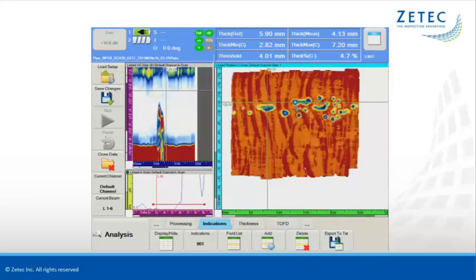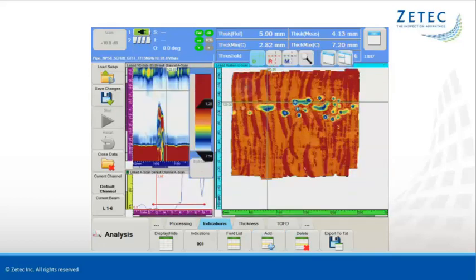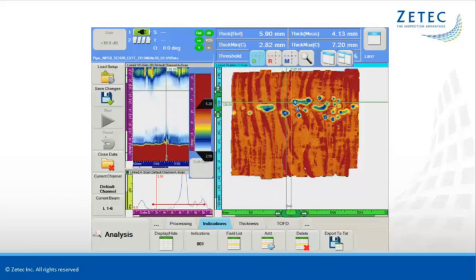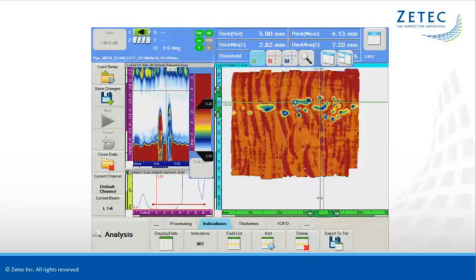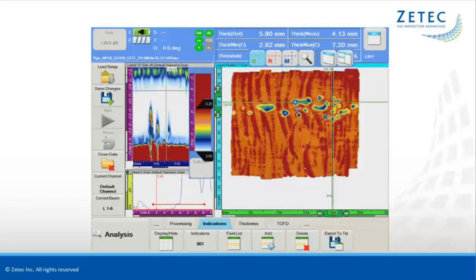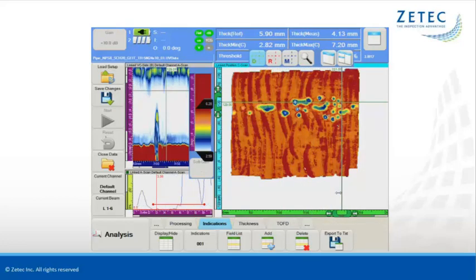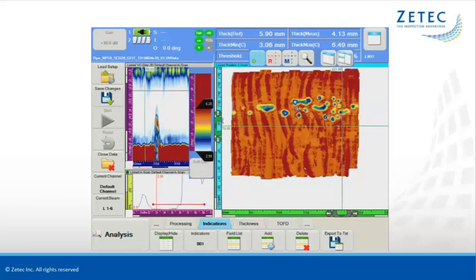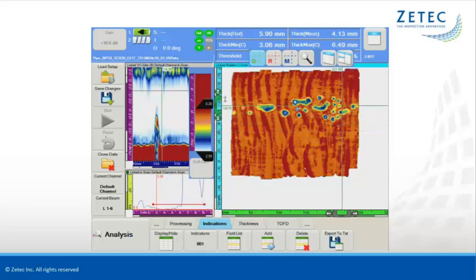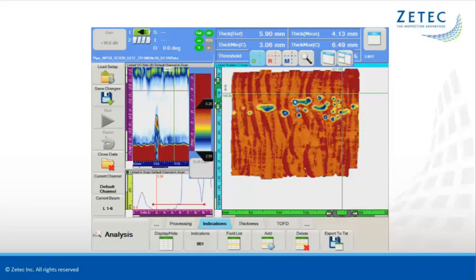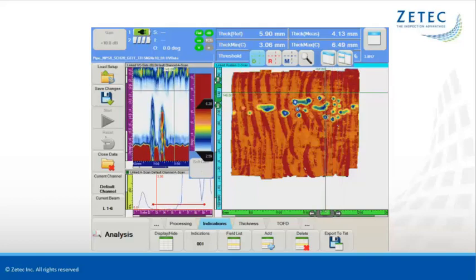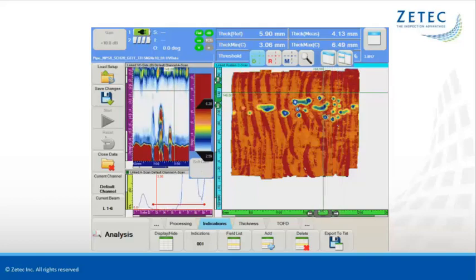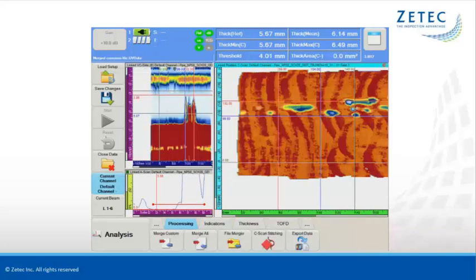Dedicated info fields for corrosion damage assessment display key information about the surface area shown on the screen. Minimum and maximum thickness in the examined region are indicated, as well as the area where the thickness is below the user-defined threshold for the given component.